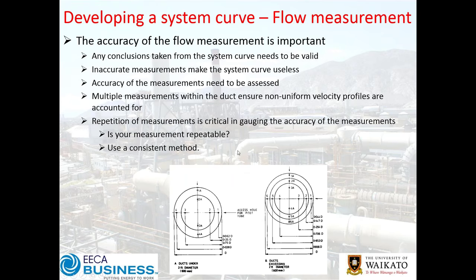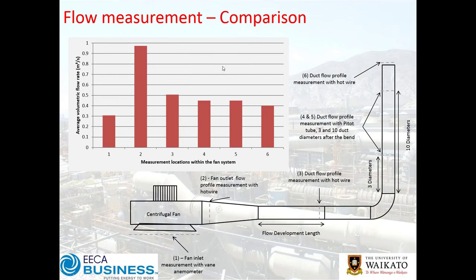If results are all over the place, generally it means something isn't right with process control or your measurement method. Here's a good example from one of our fan workshops: a centrifugal fan with a contraction in the duct, a straight section, a curved section, then another straight section and an open end to atmosphere. Measurements were taken at the fan inlet, just after the fan, downstream after flow development, around the bend, then two more and one at the outlet.